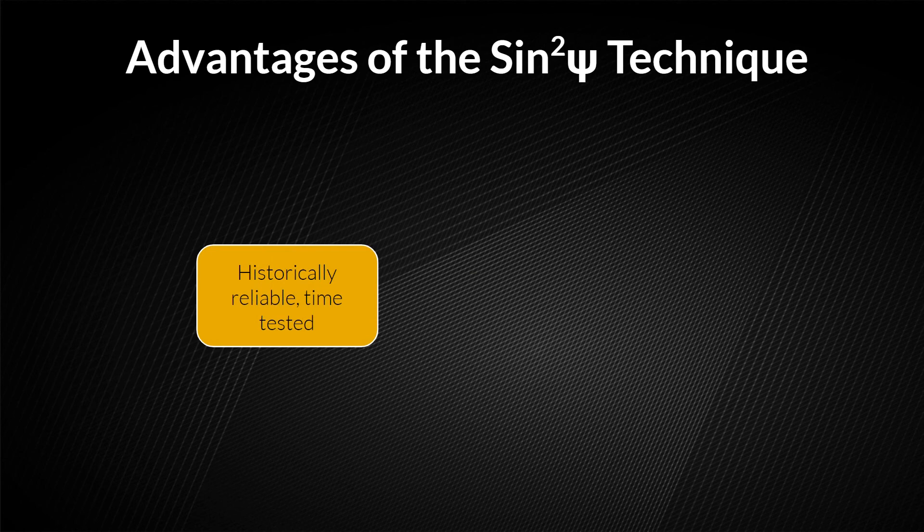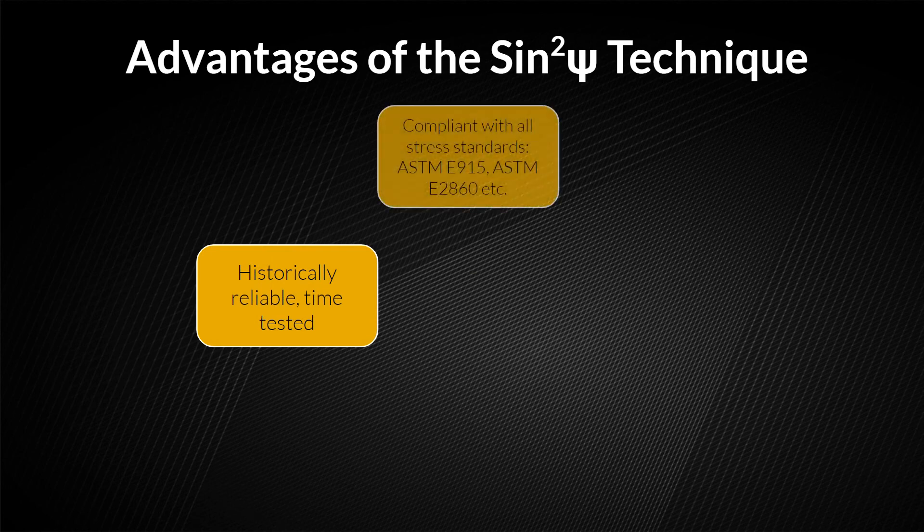This technique is known as the sine squared psi measurement technique. It is used to calculate stress because it provides the most reliable data possible. This technique is compliant with all stress standards including ASTM E915 and ASTM E2860.